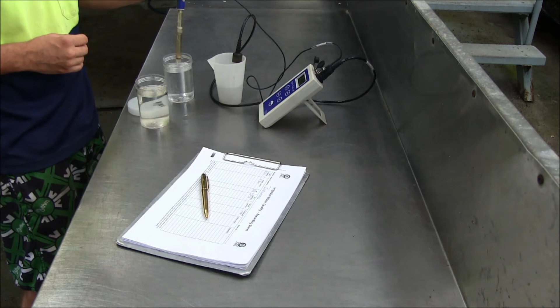Tips for maintenance of pH and EC equipment. Calibrate the meter regularly according to the manufacturer's directions. Store the EC probe dry and pH probe moist according to the manufacturer's instructions. Avoid scratching the pH probe. Store the meter in a cool, dry place and protect from the weather.